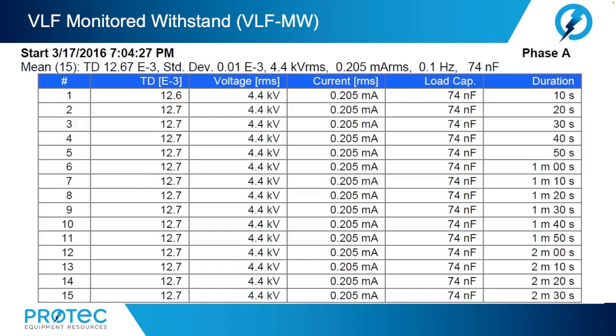So let's take a look at some test results where we performed a monitored withstand test. Here we see that the test voltage was at 1/2 U0 or 4.4 kV. We see that the standard deviation was 0.01 to the exponent of -3, which was well within the stability requirements in the tables of merit provided by the IEEE document.